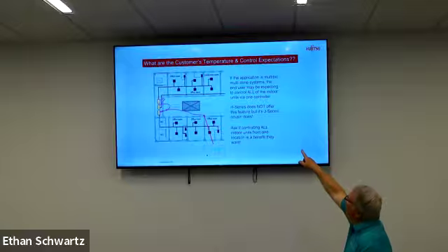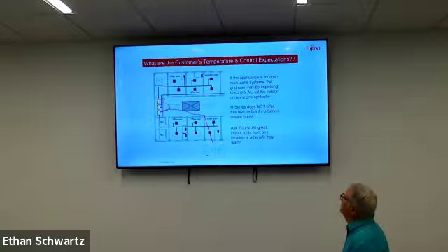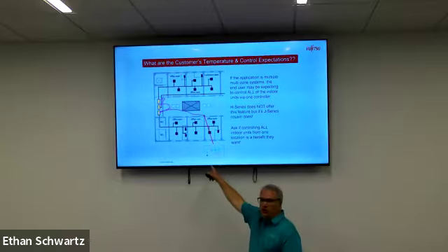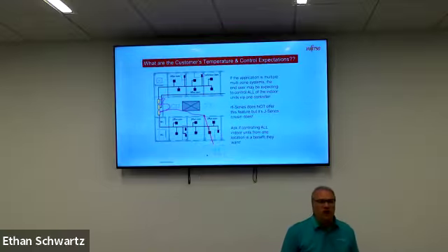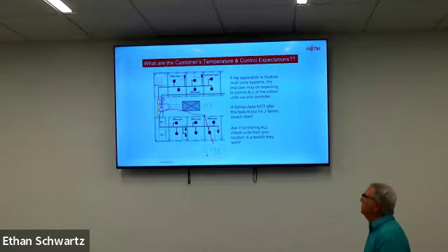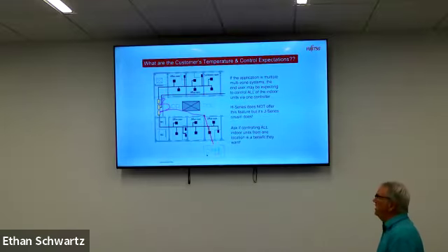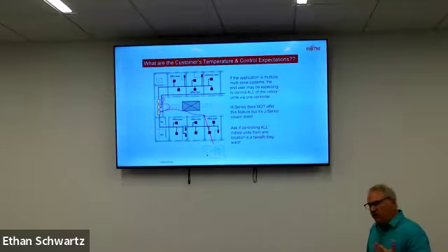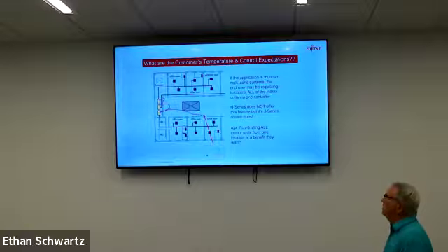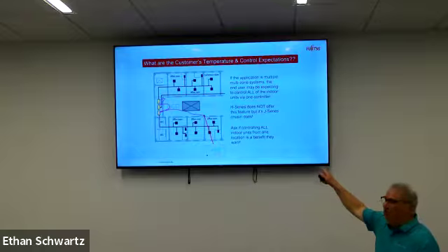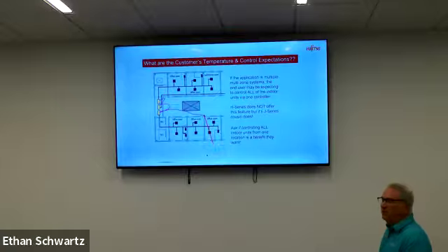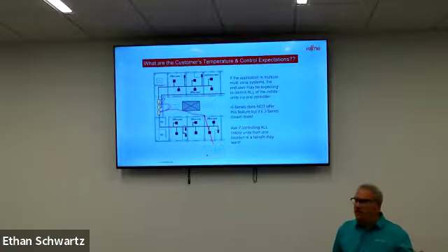Then we have, the application is multiple multi-zone systems. The end user may be expected to control all of the indoor units via one controller. Okay, this would be the centralized controller. It's going to see all of those units across all refrigeration circuits, can see up to 100 indoor units, and allow control of each one of those with different time programs and different temperature programs entered into the controller. Our H series side does not offer this feature, but its J series cousin does.